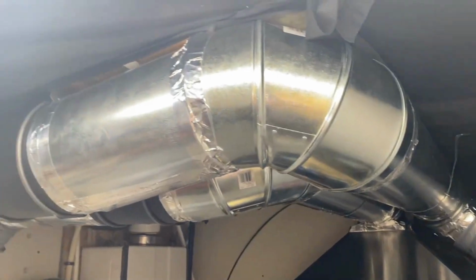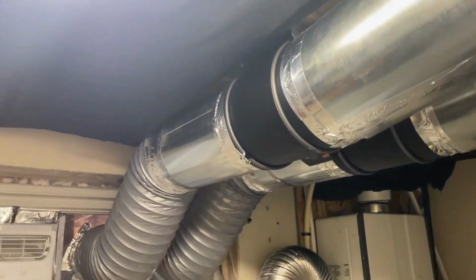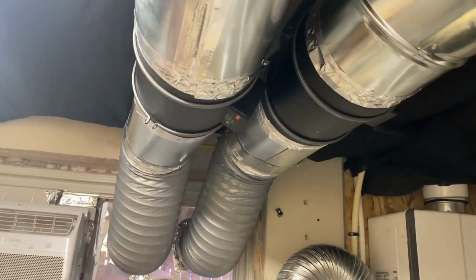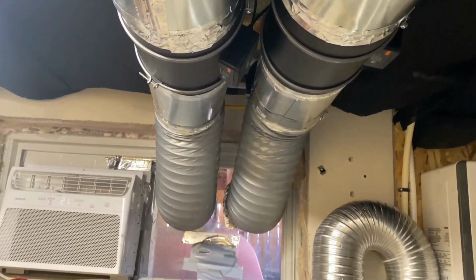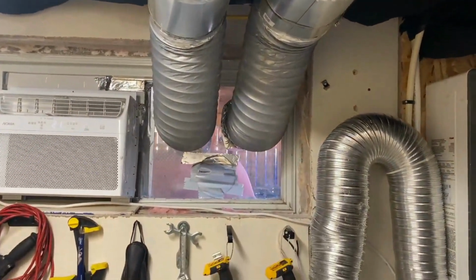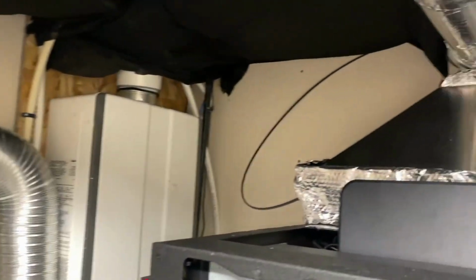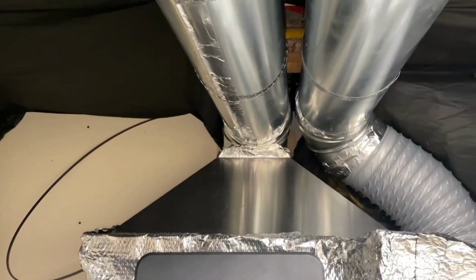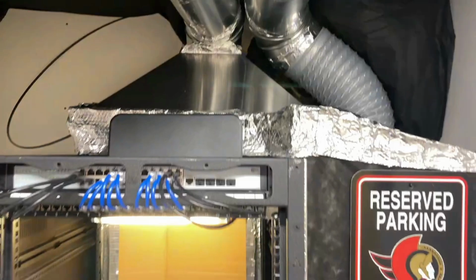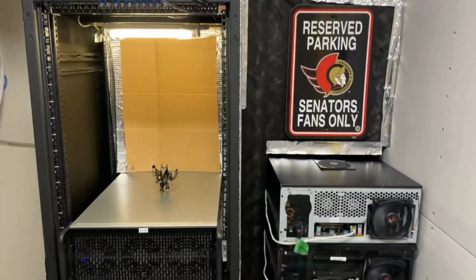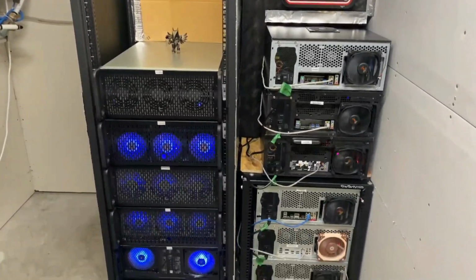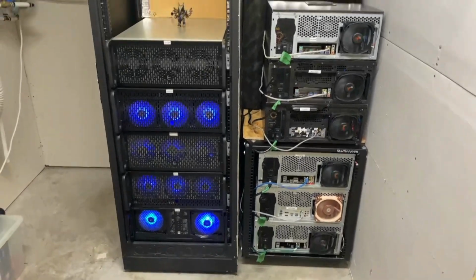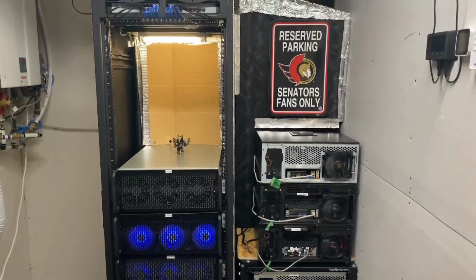In order to do that, we needed active cooling on both of those aisles. Although it's considered one aisle at the back, we needed enough exhaust, because the pressure of all that heat going out back would come back into the room otherwise. We don't want any of that coming back in, we want all of that heat shooting out of the room.